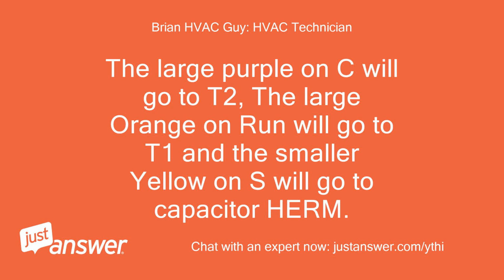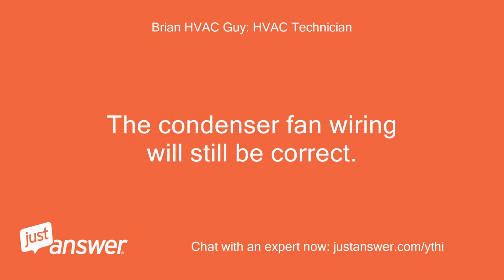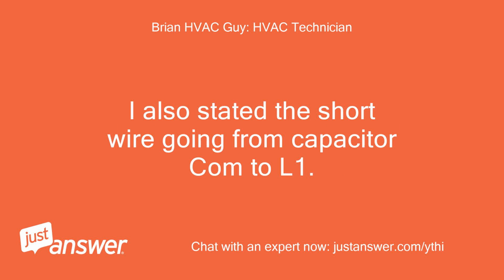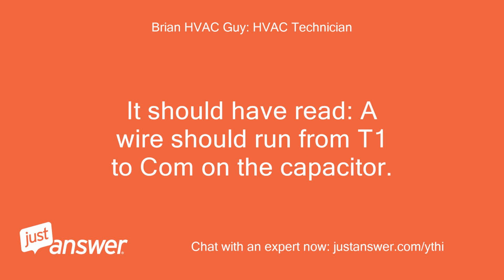The large purple on C will go to T2, the large orange on run will go to T1 and the smaller yellow on S will go to capacitor HERM. The condenser fan wiring will still be correct. I also stated the short wire going from capacitor COM to L1. It should have read, a wire should run from T1 to COM on the capacitor.